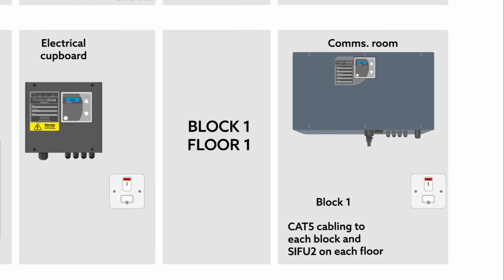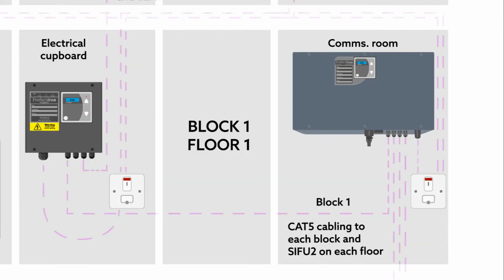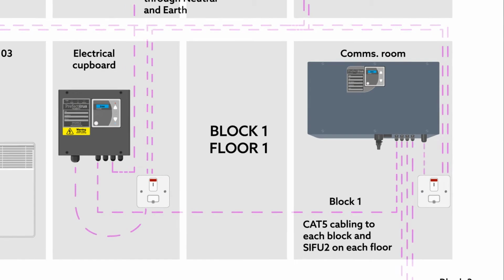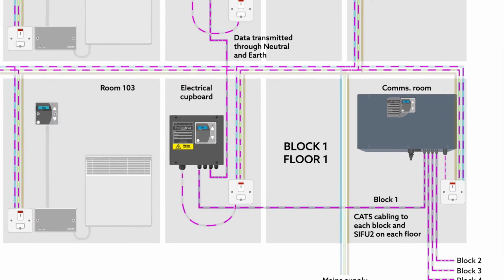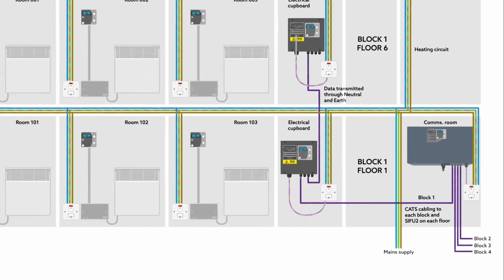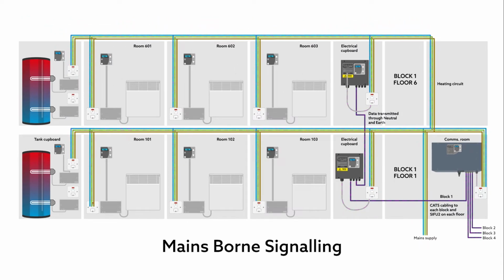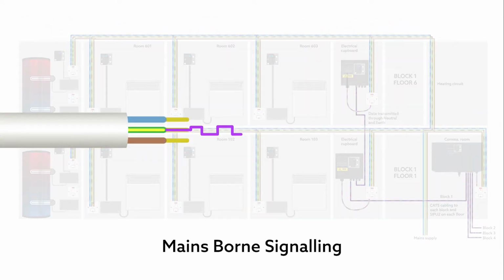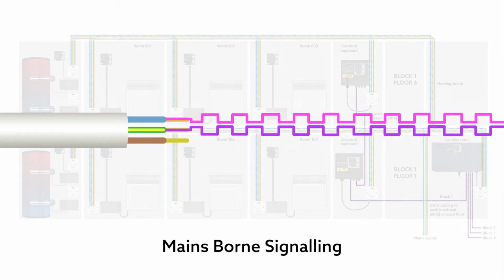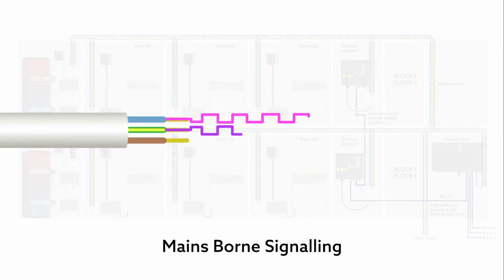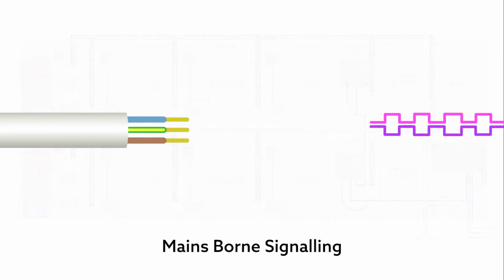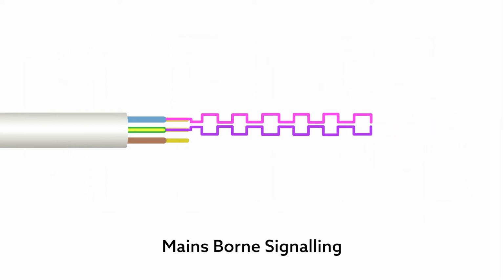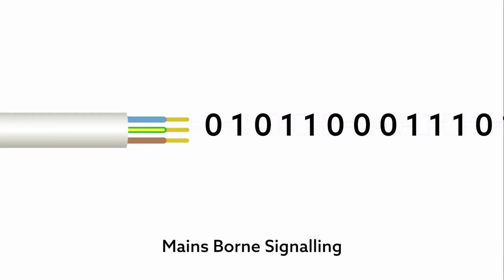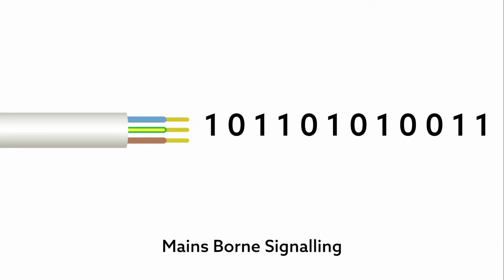The master interface unit sends and receives information and instructions via the secondary interface units to and from each room, using the site's existing electrical wiring. This is known as mains-borne signalling. Equipment connected to the electrical circuit in the building places a tiny signal on the earth and neutral wiring. Tones are transmitted along the wires. These are like two very high-frequency musical notes.